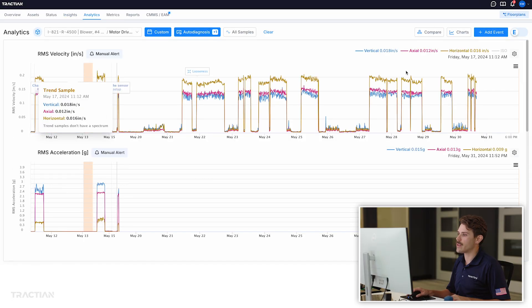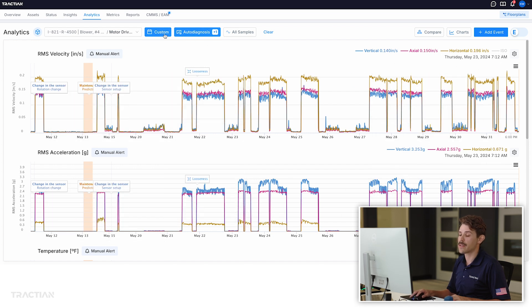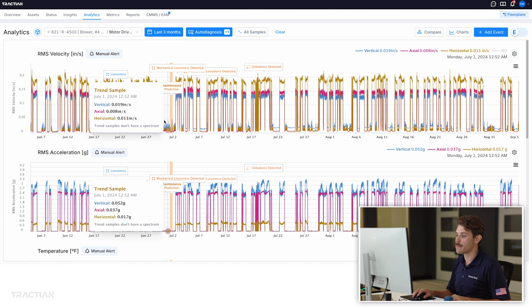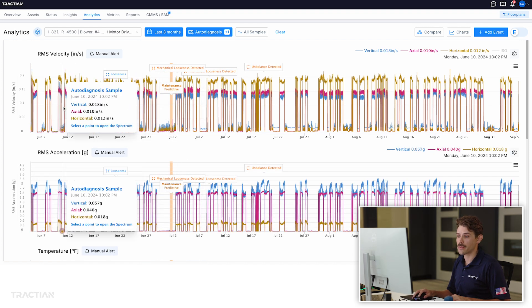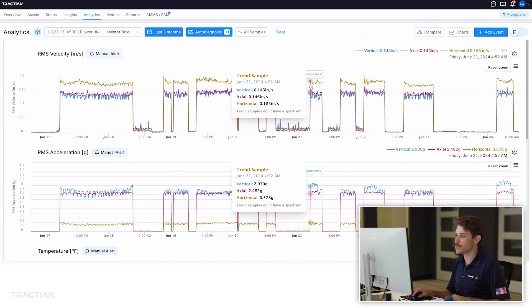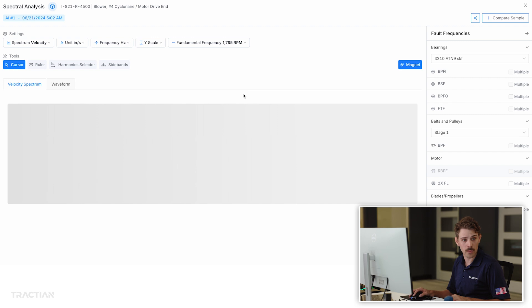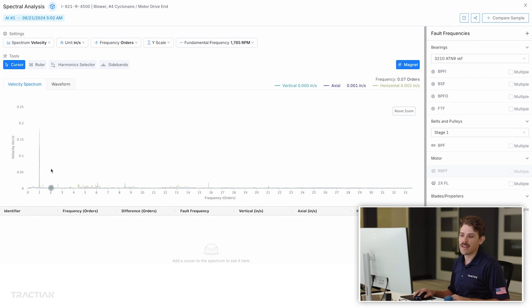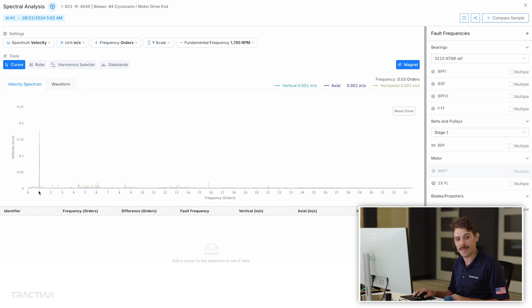When we looked at this spectrum and the initial RMS data, we don't see anything that initially jumps off the page. The RMS data has looked relatively consistent throughout its time. What I'm actually concerned with is the FFT and the spectral data that we pulled and alerted on — indicated by this graph here. This is what our vibration analysts and our artificial intelligence are looking at to diagnose specific problems. For looseness, one of the patterns we're looking for is a high one-times running speed. Running speed in this case is 1770 RPM, and this high peak at that frequency indicates a looseness problem.